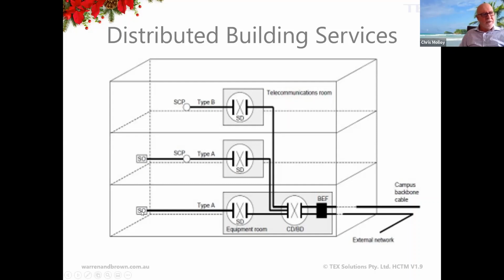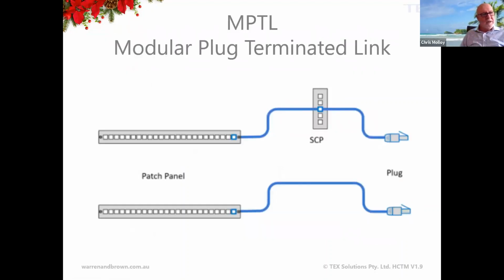Type A just goes straight from the distributor to an outlet or through a consolidation point. Type B, on the other hand, goes from the distributor to the consolidation point, and then from the SCP out that is application-specific cabling. So if you're using a Johnson control system or some form of manufactured command and control system or building automation system, there might be specific cabling that needs to be connected in its own topology going out to the field deployed devices, sensors, or whatever they happen to be, from that consolidation point. In that case, the type B cabling only defines the cabling out to the consolidation point. When I say it defines the cabling, it also defines how that cabling is installed and tested.